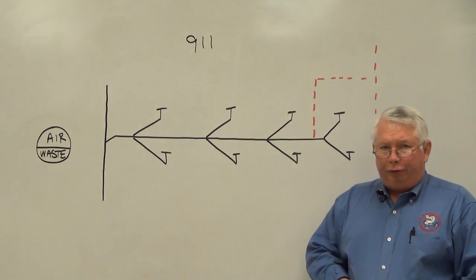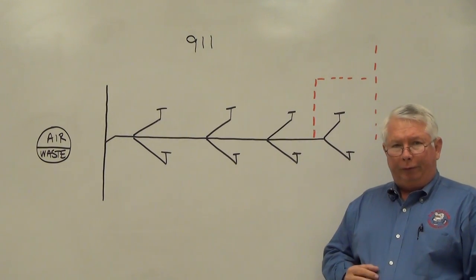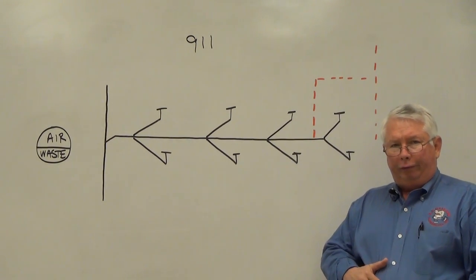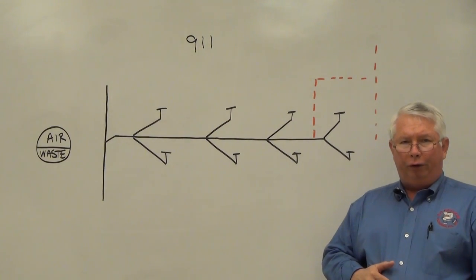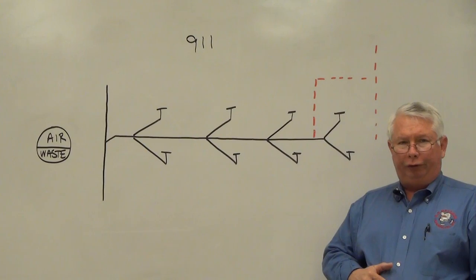The horizontal branch drain receives the discharge from the fixtures and part of the requirement of the circuit vented horizontal branch drain is for the fixtures to enter horizontally into the horizontal branch drain.